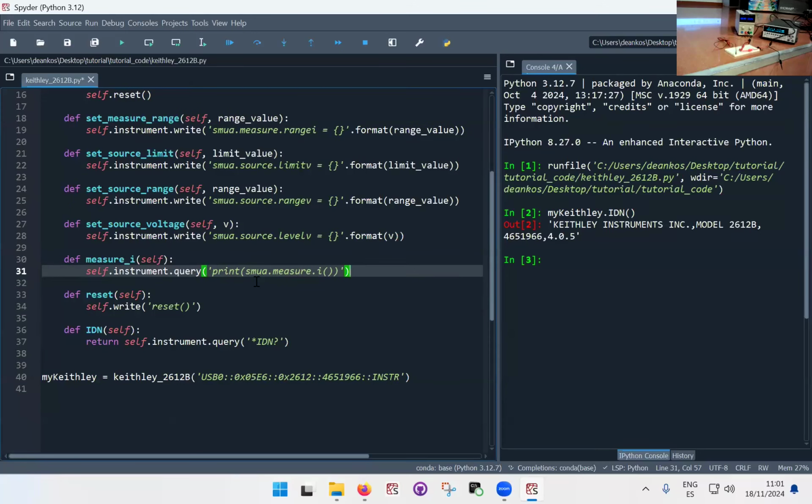There's nothing else. How do you know when you have all commands can be write and query, or do you have to know it beforehand? You should know beforehand. What's going to happen is that if you query and the instrument has nothing to tell you, it will just give you a timeout error. Generally, you can test this quickly.